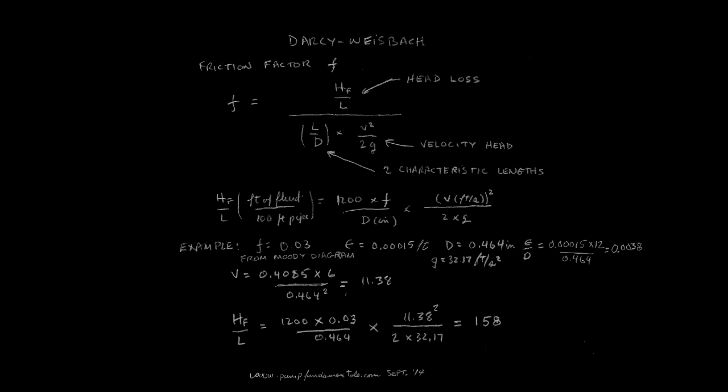The term v squared over 2g is the velocity head, which is the amount of energy that corresponds to the movement of the liquid. L is the pipe length, and d the pipe diameter.